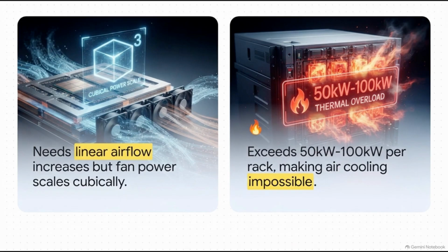To cool 100 kilowatts with air, you need to push about 15,700 cubic feet of air per minute. That's literally the equivalent of trying to force a hurricane through a 2-inch gap in a server intake. And yeah, it is exactly as loud and chaotic as it sounds.